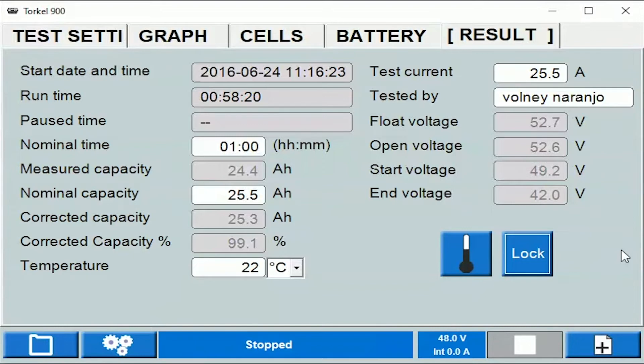This field shows the pause time. For example, if you're testing lead acid batteries, as per the procedure you're allowed to pause the test once for a certain duration. In that duration you can bypass any cells that may be approaching polarity reversal. Whenever you pause the test, a timer starts and stops when the test is resumed, and the total pause time is displayed in this section at the end of the test.